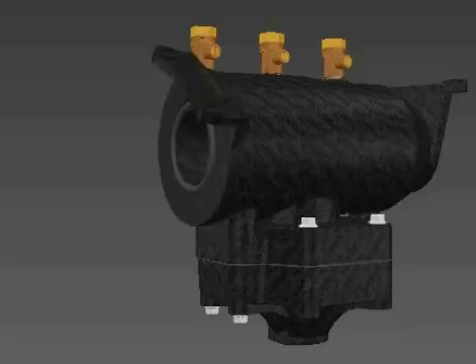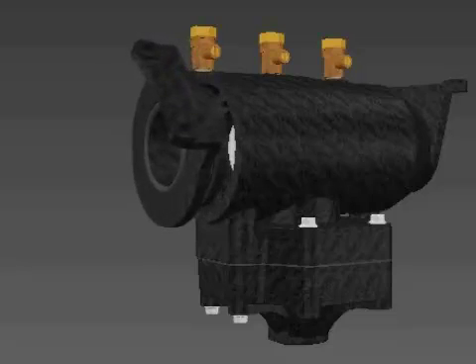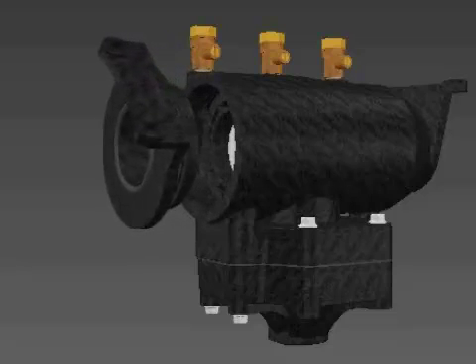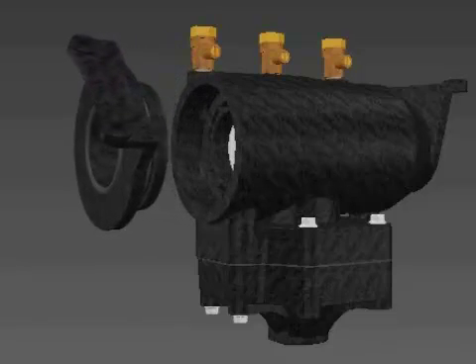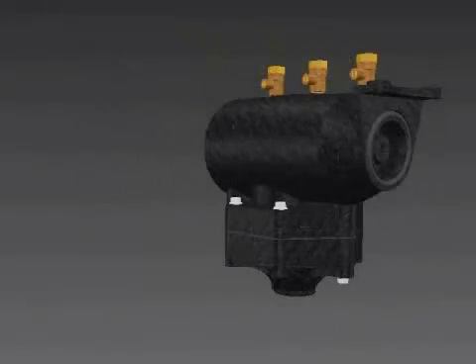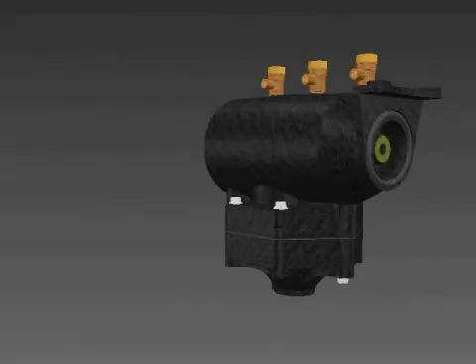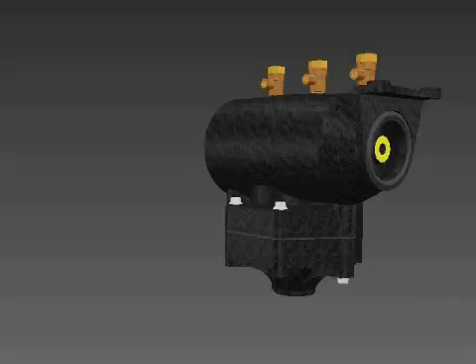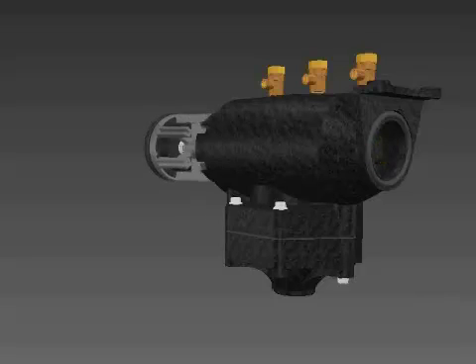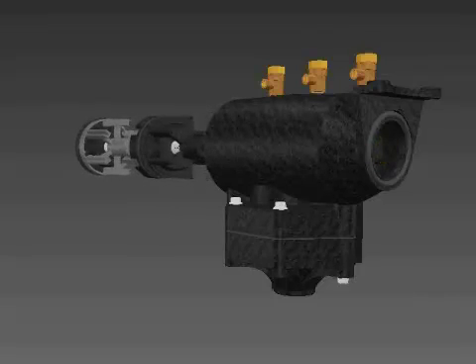Twist the sleeve at the end of the body and then pull to remove from the body. Remove the checks from the housing by pushing on the check visible at the small end of the housing using your thumb or the handle of a small screwdriver.